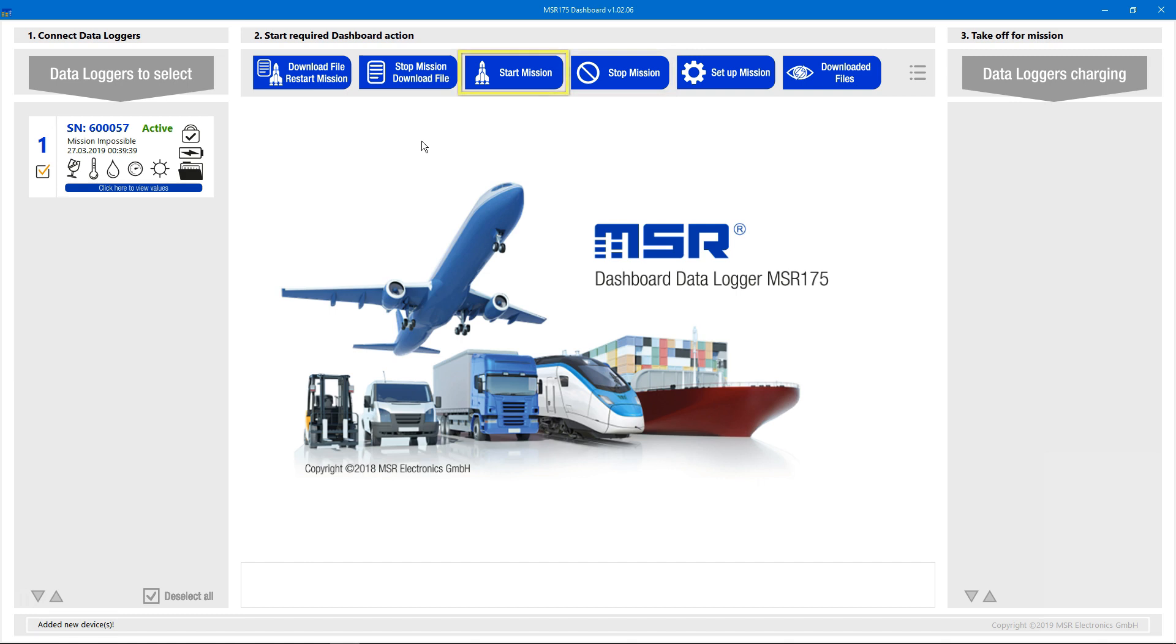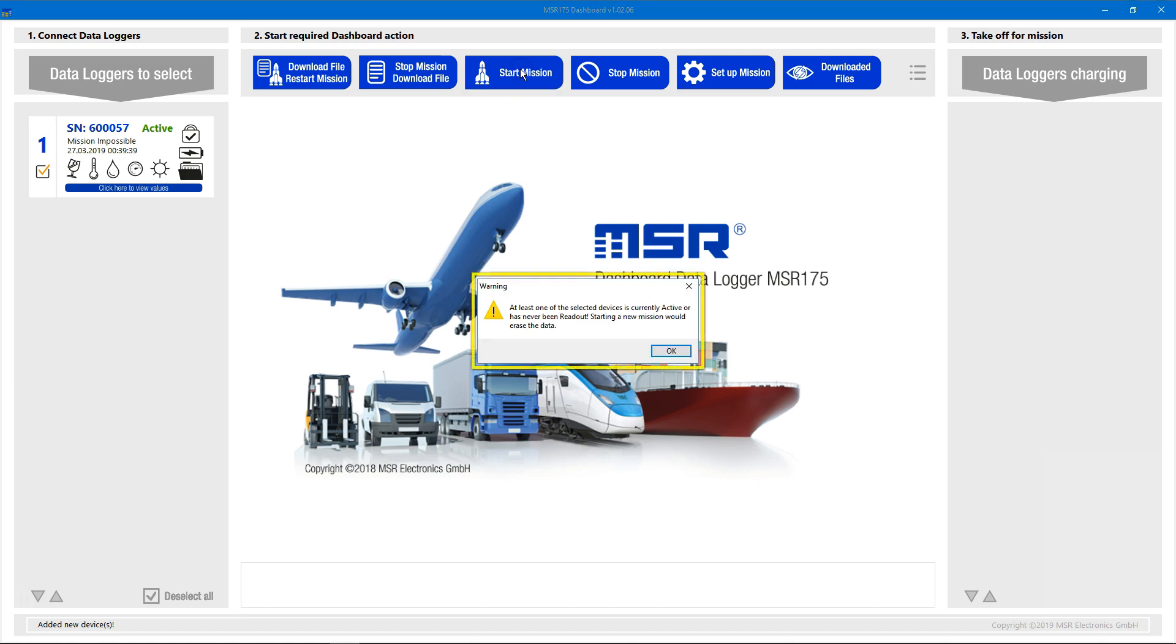The start mission button, although active, will not let us start a new mission on this device since we didn't download the contained data yet. We would lose this data since the logger's storage is always cleared when starting a new mission.